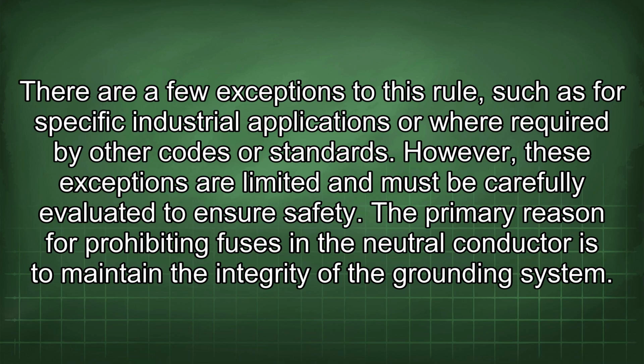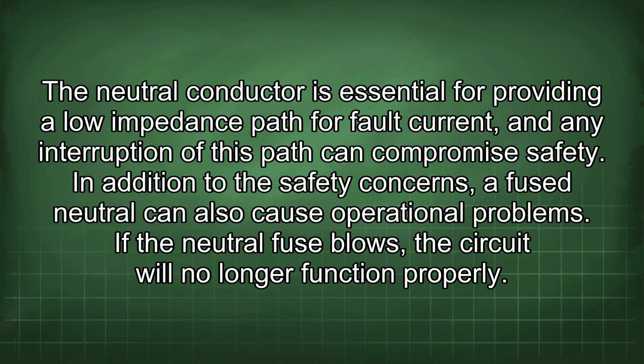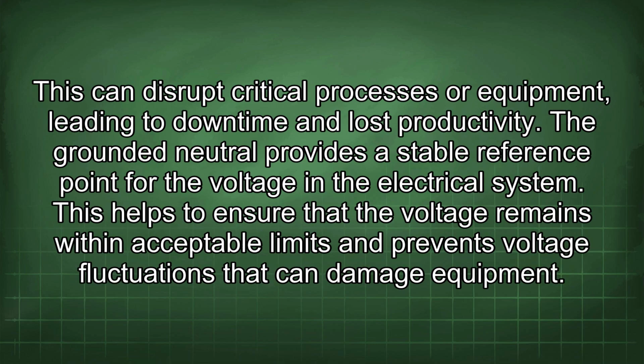The primary reason for prohibiting fuses in the neutral conductor is to maintain the integrity of the grounding system. The neutral conductor is essential for providing a low impedance path for fault current, and any interruption of this path can compromise safety. In addition to the safety concerns, a fused neutral can also cause operational problems. If the neutral fuse blows, the circuit will no longer function properly. This can disrupt critical processes or equipment, leading to downtime and lost productivity.